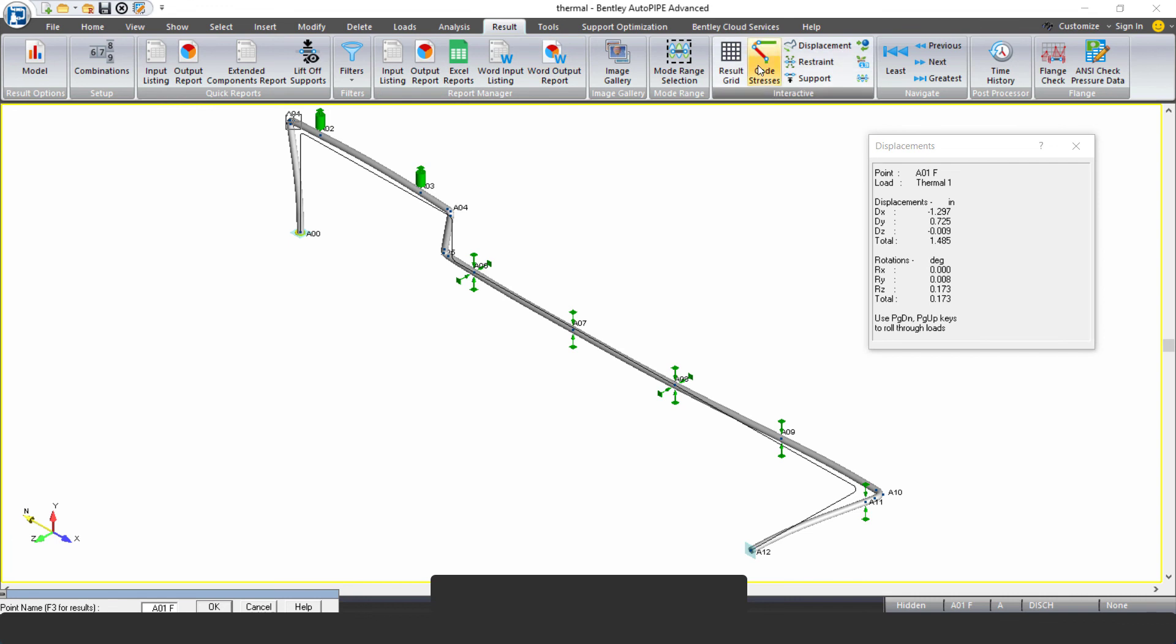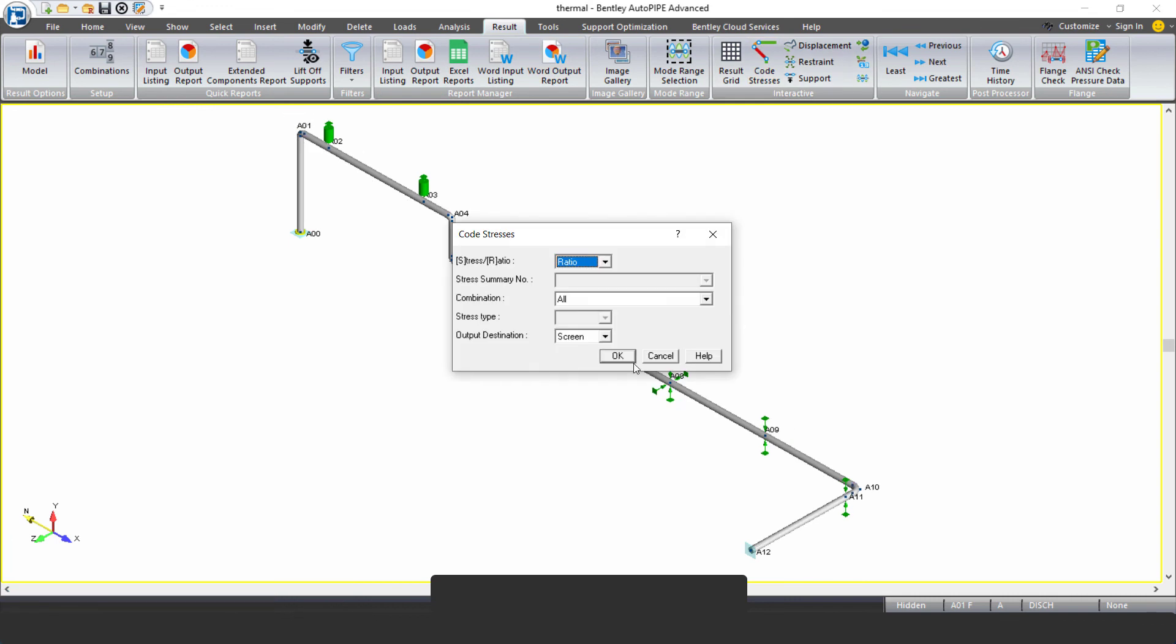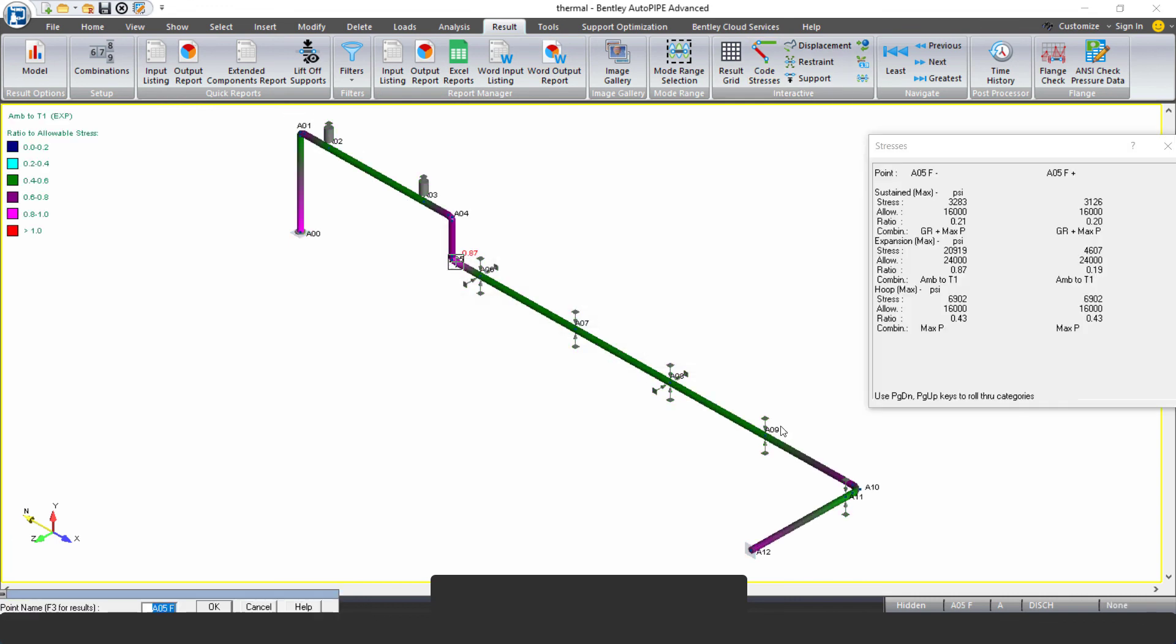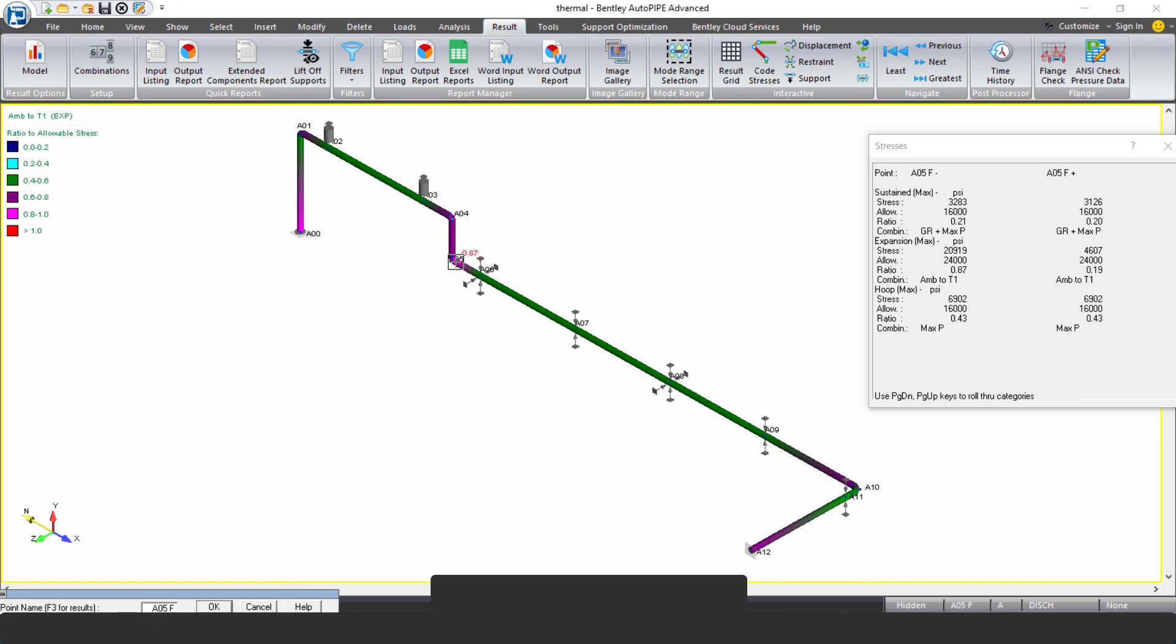If we look at our code stresses, we don't have any overstressing. If I look specifically here, this is looking at the expansion case here. And we don't have overstressing, but we have some up towards 0.9 ratio compared to our allowable of code stress in the expansion case, because there is a lot of growth occurring within these two rigid anchor points. But we are allowing it to grow. So let's take this.